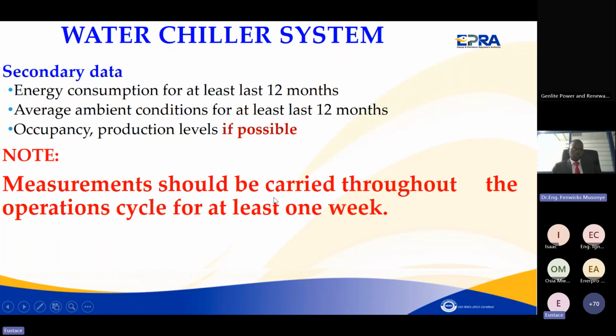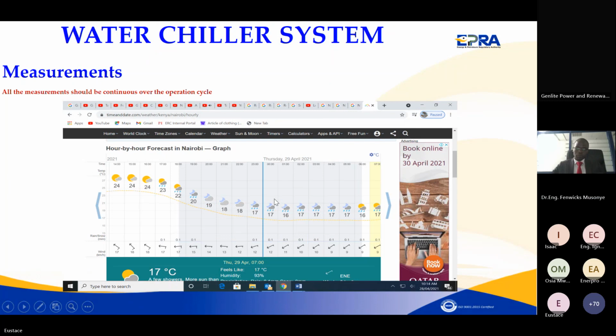Because I've seen in most cases, people auditing air conditioning systems do the regression analysis vis-a-vis what we call cooling degree days or heating degree days. They forget the humidity. If you learn about degree days, they are normally used for approximation - they don't give you the real figures because they don't take into consideration the humidity of a given place.